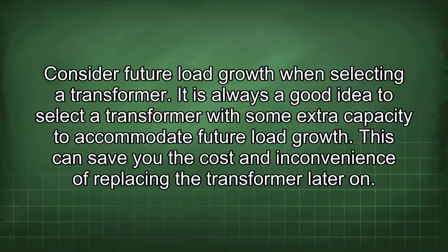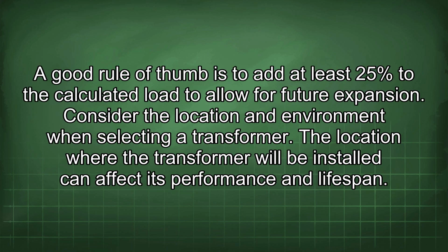Consider future load growth when selecting a transformer. It is always a good idea to select a transformer with some extra capacity to accommodate future load growth. This can save you the cost and inconvenience of replacing the transformer later on. A good rule of thumb is to add at least 25% to the calculated load to allow for future expansion.